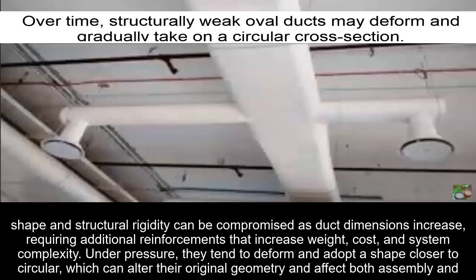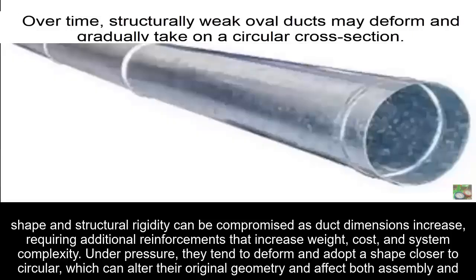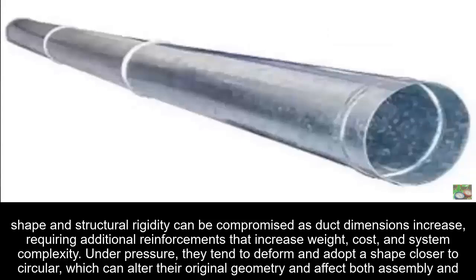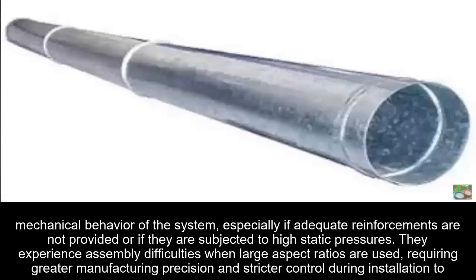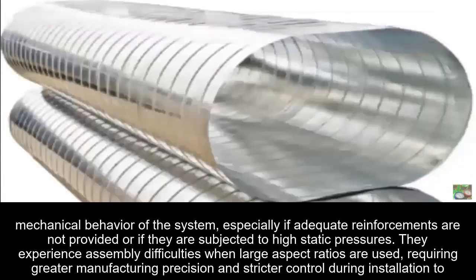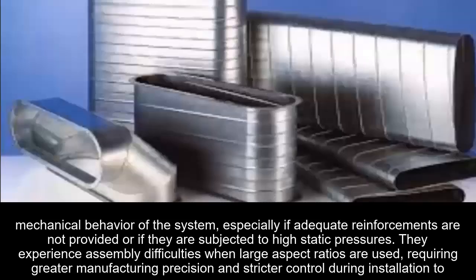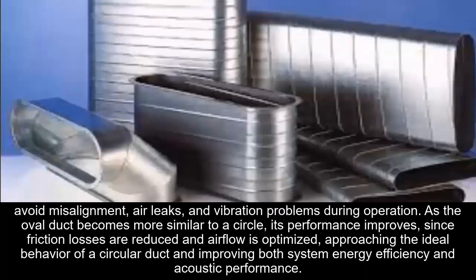Under pressure, they tend to deform and adopt a shape closer to circular, which can alter their original geometry and affect both assembly and mechanical behavior of the system, especially if adequate reinforcements are not provided or if they are subjected to high static pressures. They experience assembly difficulties when large aspect ratios are used, requiring greater manufacturing precision and stricter control during installation to avoid misalignment, air leaks, and vibration problems during operation.